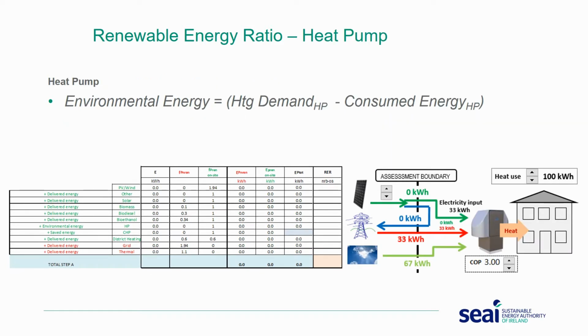And with regards to heat pumps, things have actually changed. The calculation methodology has changed from what was there previously. And again, what we're doing is just going with the ISO standard, so we're moving towards the European standards. And if you look over in the corner, if you have a heat pump that has a coefficient of performance of 3, if you get 100 kilowatt hours of heat out of that, that means 33 kilowatt hours of electricity or whatever the fuel is going into it. What it means in terms of the renewable energy proportion is that 67 kilowatt hours of it is renewable. It's what is regarded as the environmental energy from the heat pump. Now that is more favourable than the old methodology that used to be there for calculating the renewable contribution from heat pumps.